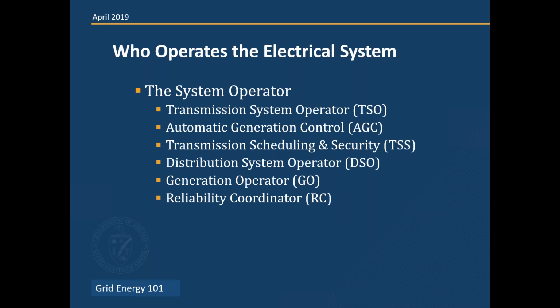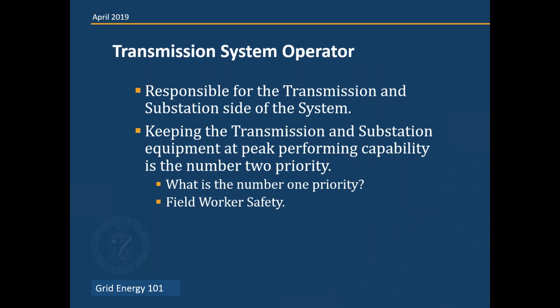Next slide, please. So the transmission operator, he's the guy that is responsible for the transmission, the substation side of the house, and the higher voltage type of equipment. Keeping the transmission substation equipment at peak performing capability is the number two priority. His number one priority is the safety of the worker, the safety of the public, and the safety of the field worker. And what I mean by the field worker, I mean the electricians, meter relay technicians, and the line crews. Next slide.